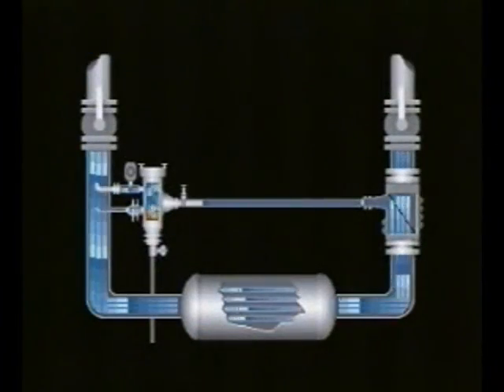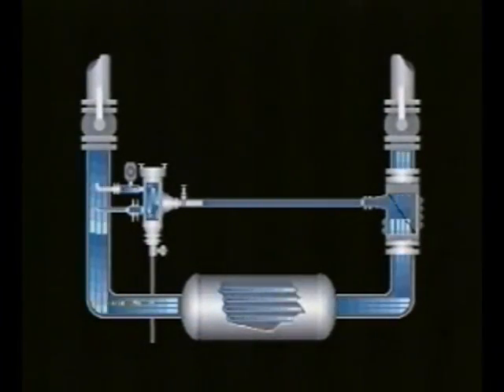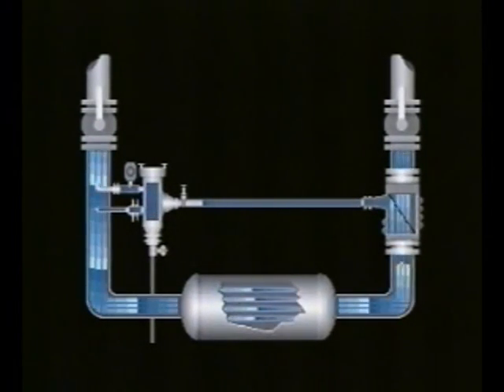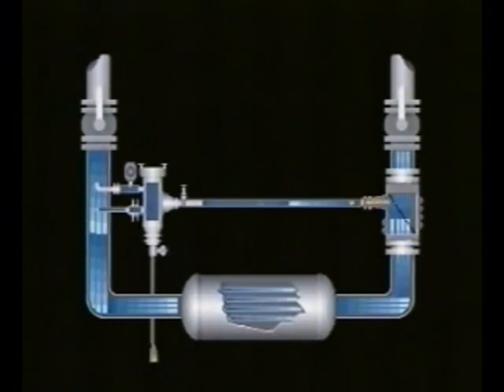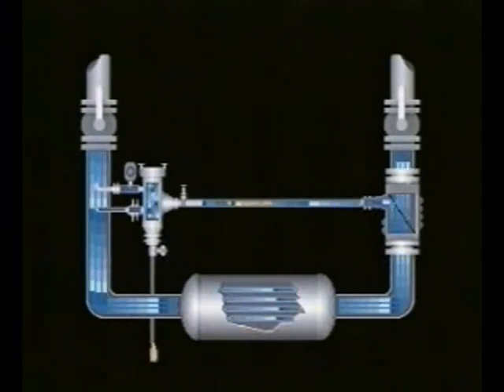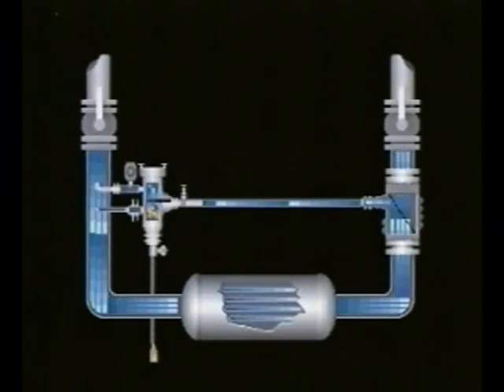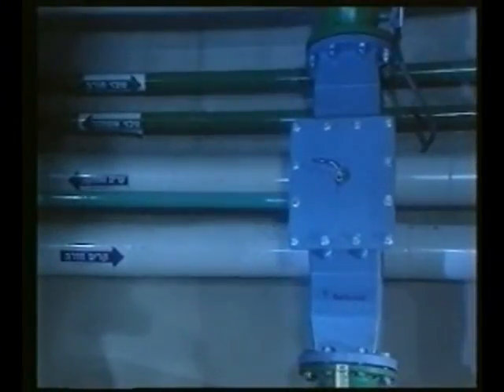The system is a fully automated hydromechanical process recycling sponge balls with special properties through the condenser's tubes at preset intervals. Let's see how it works. The system has three main elements: an injector, a ball trap, and a computerized controller.